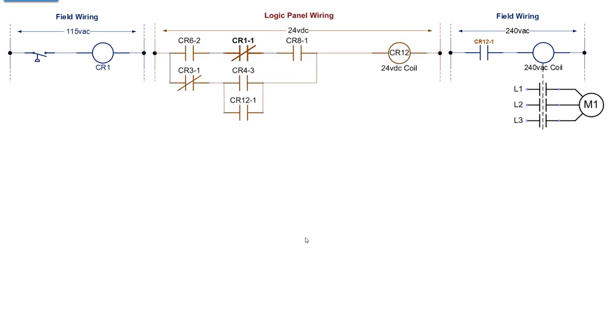And here's the logic for that relay CR12. We have six relays. We don't see the coils here. We're just grabbing one little chunk of relay logic, one field device, which is CR1, the pressure switch, hydraulic reservoir, and that pressure switch closes when the hydraulic pressure is up to the set point. In the field wiring, when we close the contact CR12, that runs the motor to pump the pressure up.